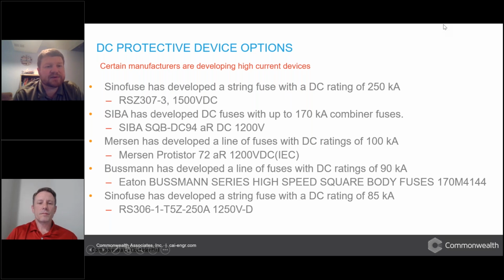So Chris, thanks for the intro on the steady state. Very good presentation. So I think what we want to talk about now is we're going to get into the DC and the transient analysis portion. If we're getting into the DC world and we're seeing fault currents and arc flash times that don't work for our project, we're basing all that on this idea of prospective fault current. So if the fault's allowed to persist and the fuse does not clear the fault by the time the fault gets to its total available fault current, that's where that steady state analysis is very useful.